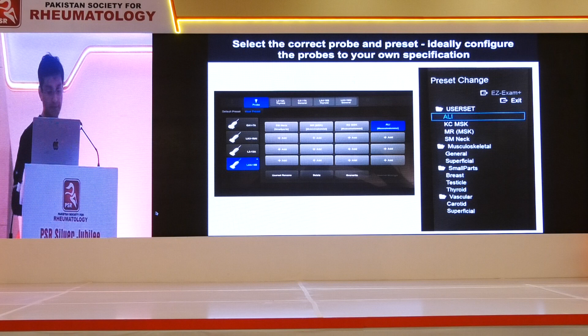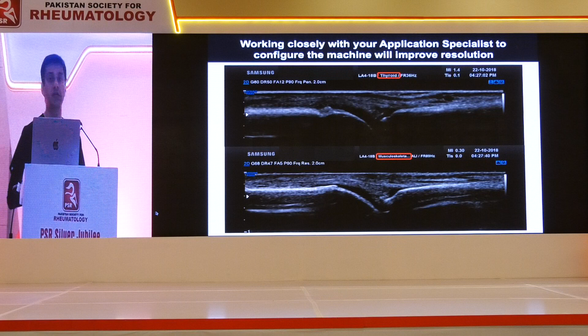You can see that if you put on a thyroid preset, if you look at the fuzziness of that cartilage, of that proximal phalanx, and then you look at how crisp this is, you'll see that nothing else is changing. The focal zone is the same, everything else is the same. All we've done is just change the preset, and you can see how much crisper your image becomes by choosing the right preset if you've adjusted it appropriately.